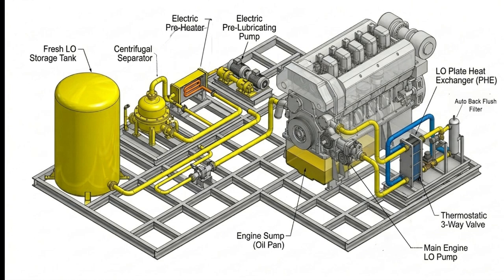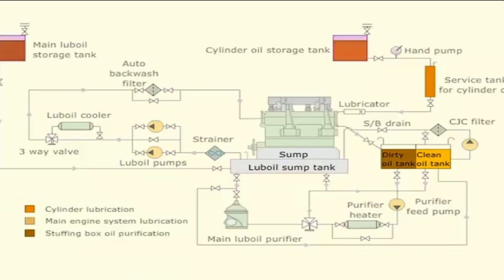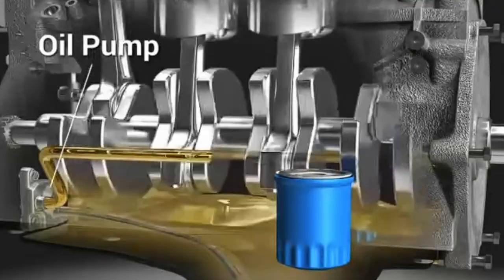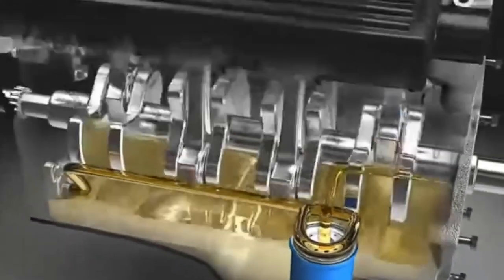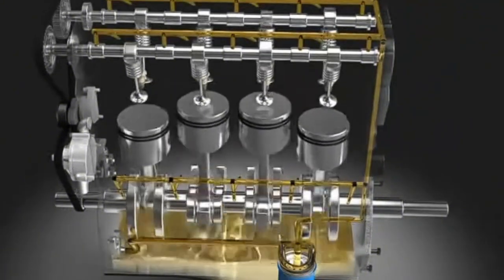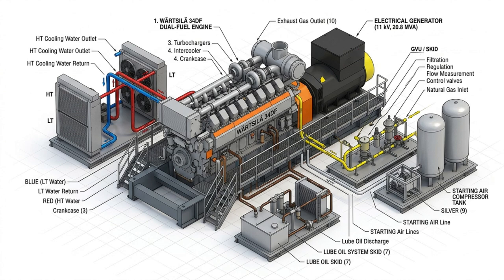To conclude our technical overview, let us look at the lube oil system, a critical utility that protects the engine from friction, wear, and excessive heat during operation. Before engine startup, an electric pre-lubrication pump establishes oil pressure throughout the engine. Once the engine reaches operating speed, the mechanically driven main lube oil pump takes over continuous oil circulation. The oil then passes through filters and the lube oil cooler, which is supported by the LT cooling system, before being recirculated back to the engine. This combination of reliable lubrication, filtration, cooling, and monitoring helps maximize engine reliability, performance, and operational life.